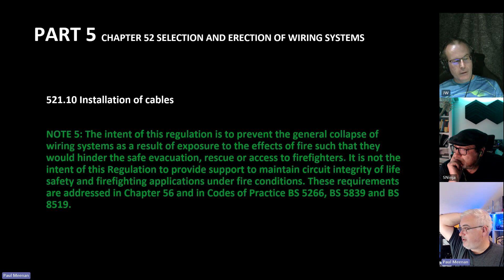521.10 is about non-sheathed cables for fixed wiring being enclosed in conduit, ducting, or trunking. This doesn't necessarily apply to a protective conductor. Non-sheathed cables are permitted if the cable trunking provides at least a degree of protection of IPXXD or IP4X - that seems to be an alteration - and if the cover can only be removed by means of a tool. Then there's loads of other bits below it, and it says wiring systems shall be supported such that they will not be liable to premature collapse in the event of fire. This one regulation has caused a lot of arguments and debates over the years.